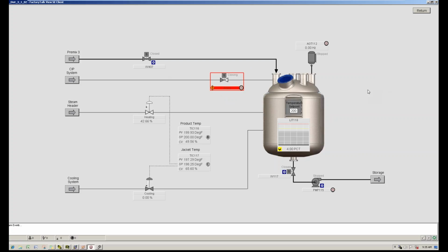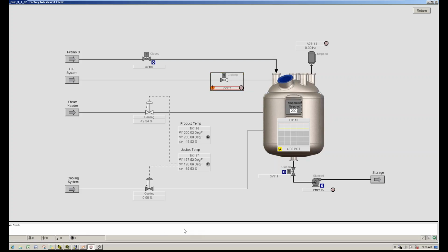That's telling us that there's an alarm active on that valve. The text, hopefully you can see next to the solenoid symbol, is saying that the valve's closing. So the valve's trying to close, but it hasn't yet got a closed feedback. And so that's brought up a transit alarm saying that the valve has taken too long to transition. Down the bottom of the screen here, we've got an alarm banner, but you'll notice that there's no alarms in there at this point in time.